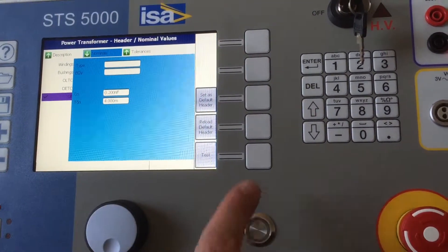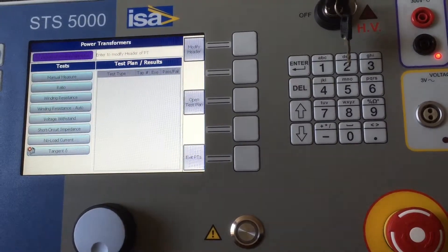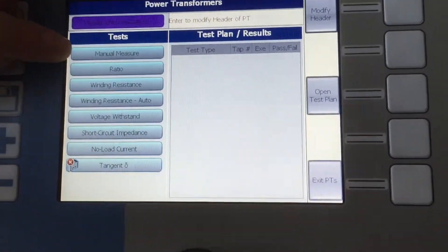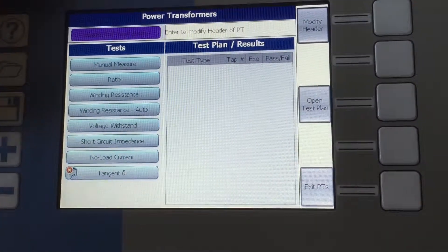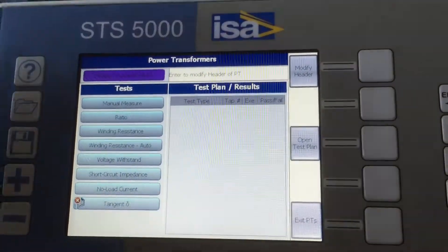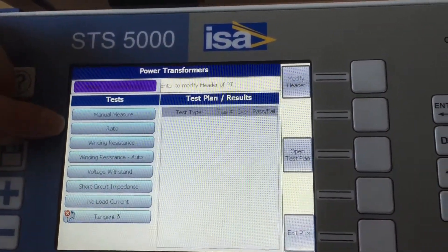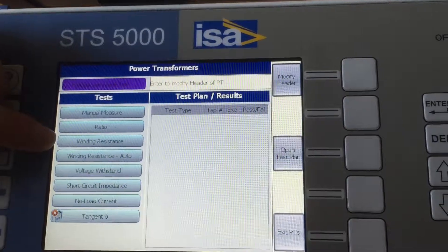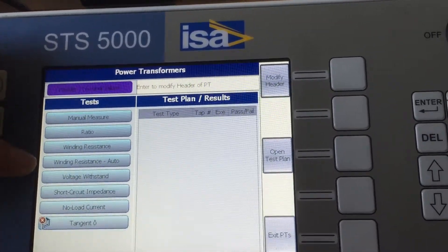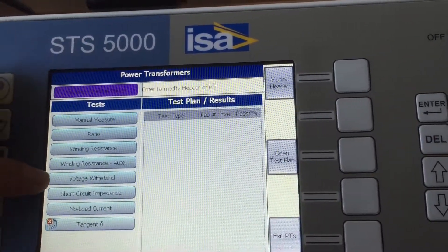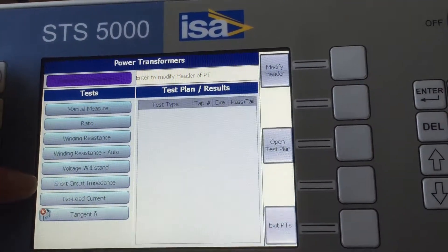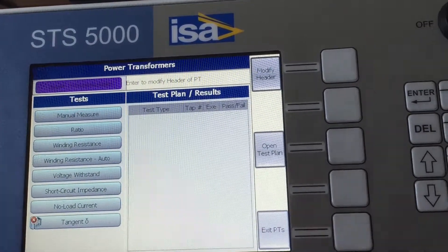Once that is done, the set of tests you can do for a power transformer is of course as always manual measure which means any generation and any measurement which you decide, ratio of a power transformer, winding resistance, winding resistance in automatic mode, voltage withstand, short circuit impedance, no load current and tan delta.